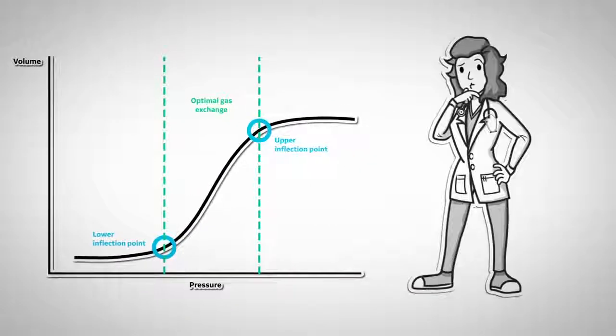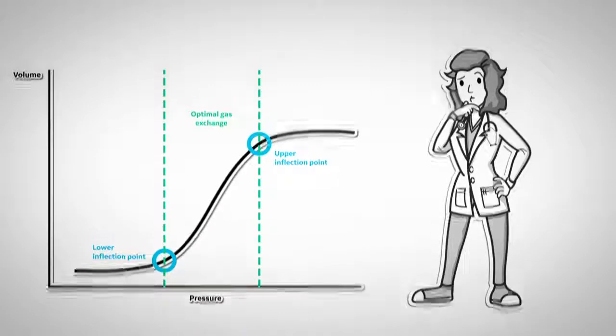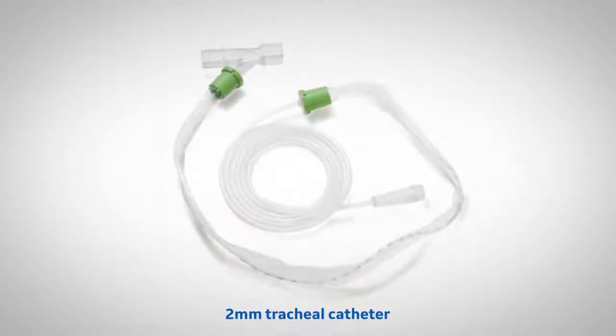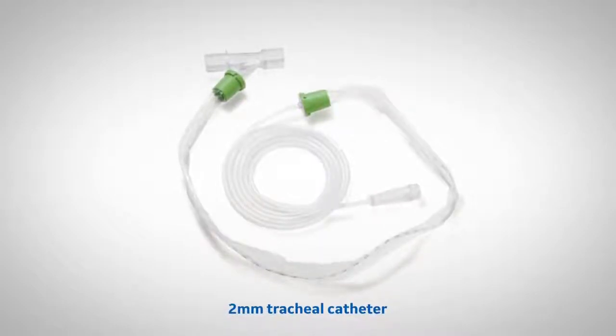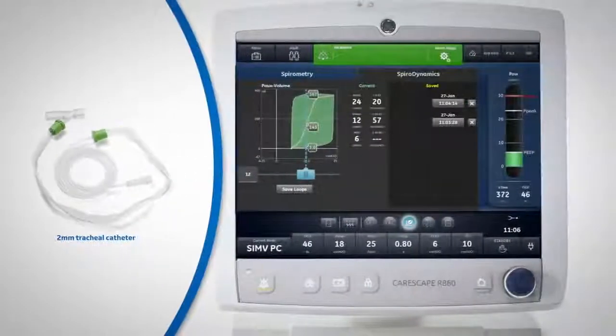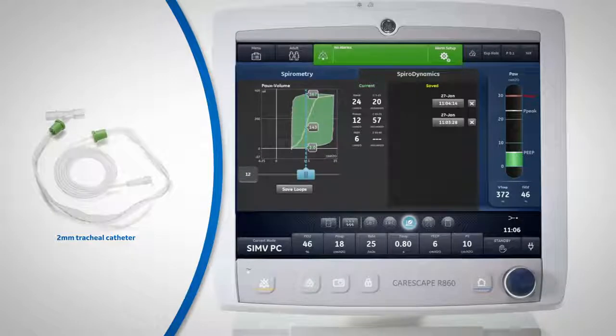Sometimes it can be difficult to visualize the upper and lower inflection points using the pressure-volume loop. The CareScape R860 offers measurements on tracheal pressures and intrinsic PEEP via a small 2mm tracheal catheter and the use of the SpiroDynamics clinical decision support tool.